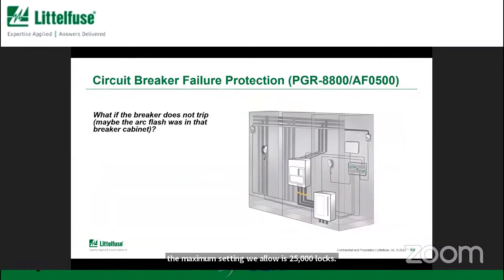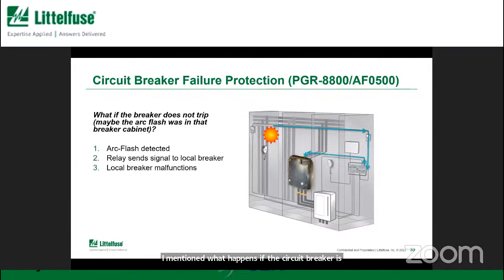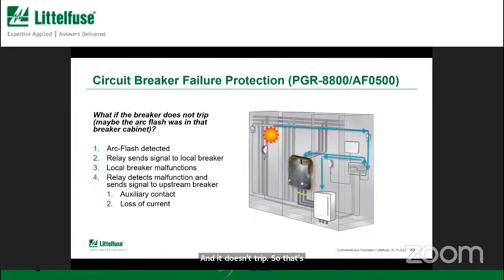So I mentioned what happens if the circuit breaker is damaged and it doesn't trip. So that's why we offer the ability to detect that malfunction and send a signal to an upstream breaker. So we do that by checking the auxiliary contact, or if you're using current with the 8800 relay, we can check and see if the current has gone away.